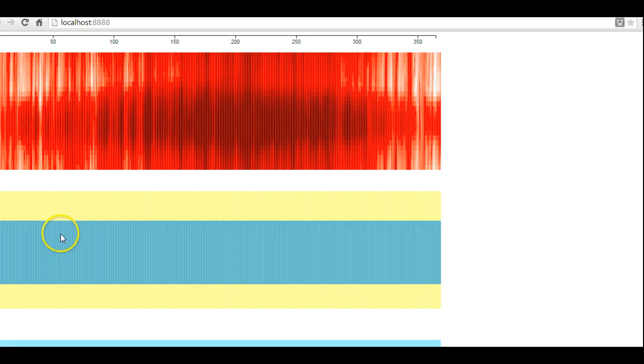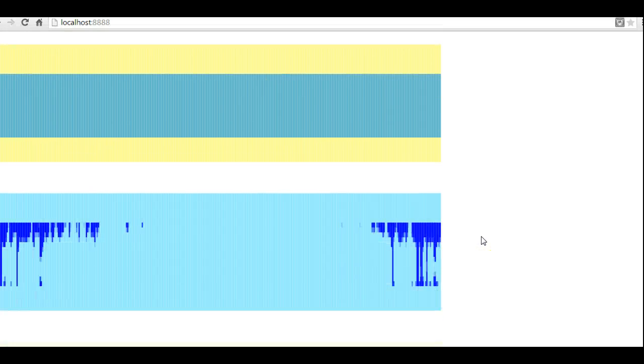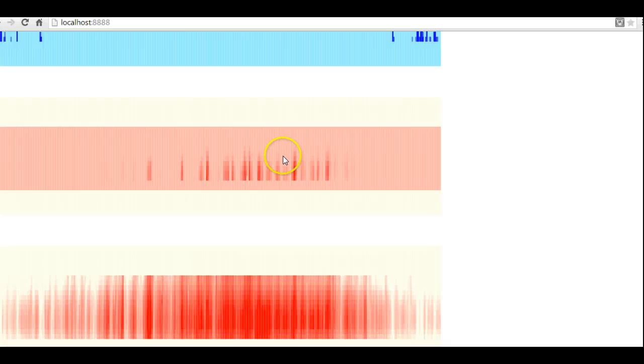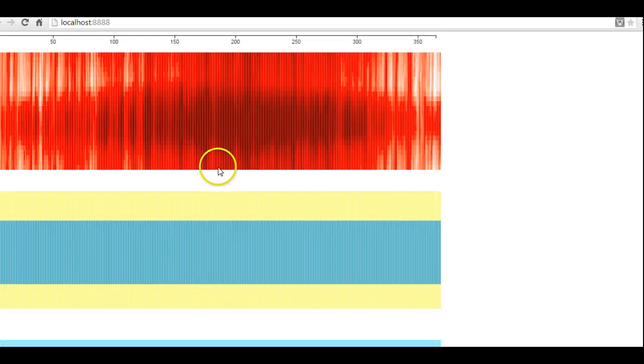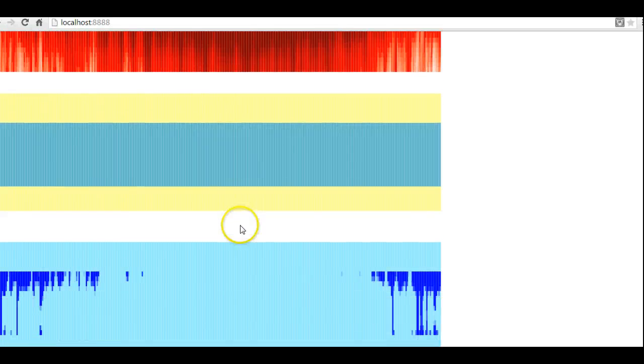you can see now that the outside air flow rate is much more uniform, and it's shutting off at night. We also see that the economizer status is pretty much on all the time, but that's okay. The status has nothing to do with the flow, so it's kind of good that I actually plotted these two things separately, because even though the status is essentially on most of the time, it doesn't really matter. And then you can see our fan here is kind of controlling more regularly. And then what's even nicer is that the cooling coil appears to be working a lot more smoothly now too. I wish I had a bigger screen so I could superimpose these images on top of one another. But I think you kind of get the idea here.